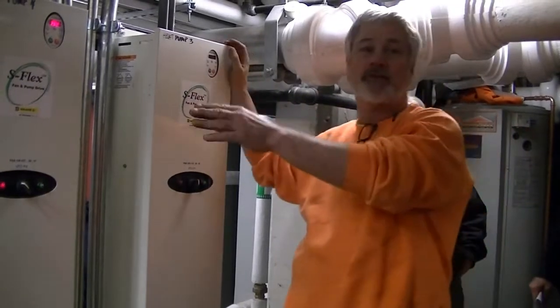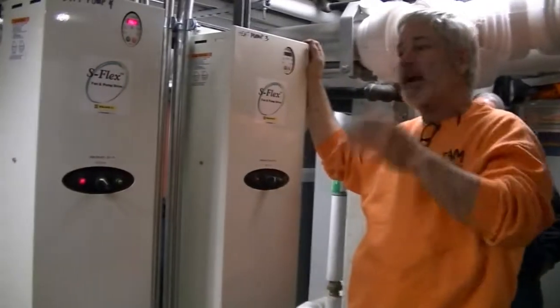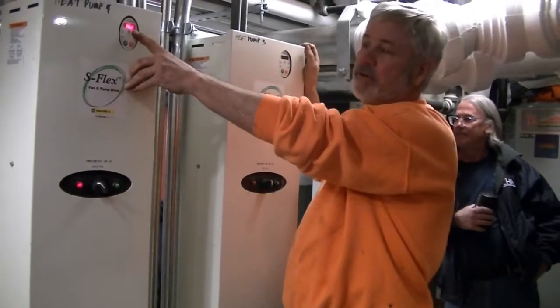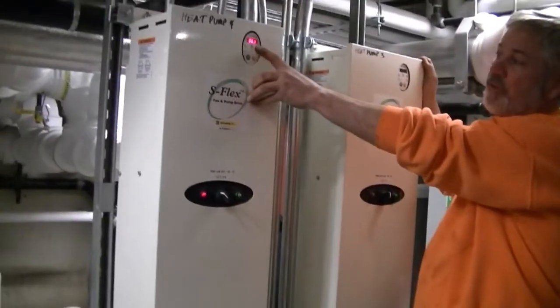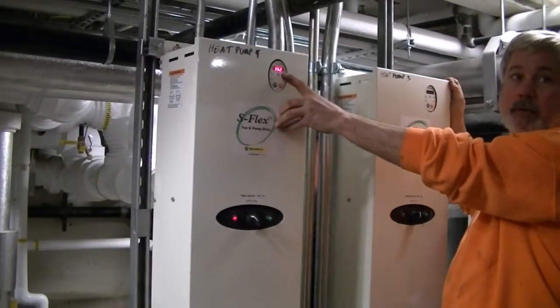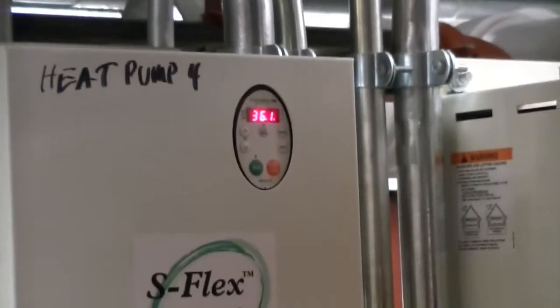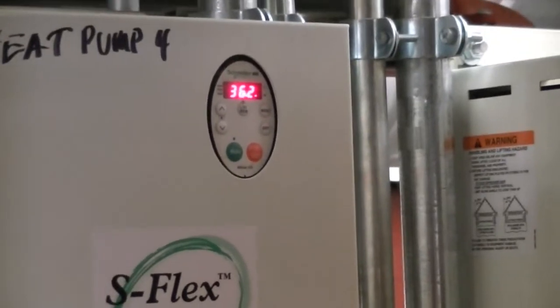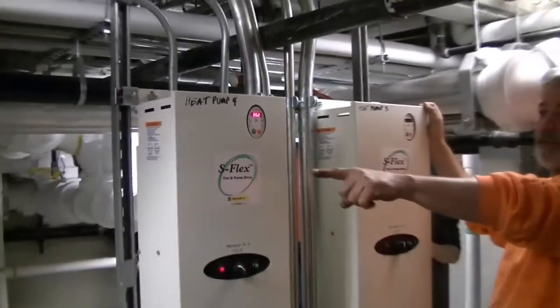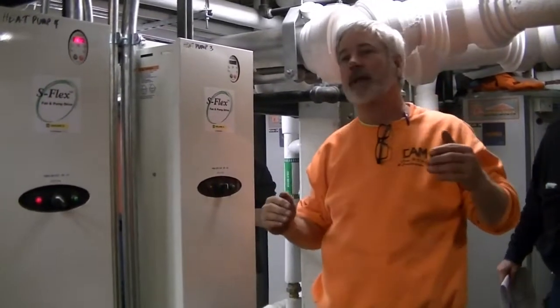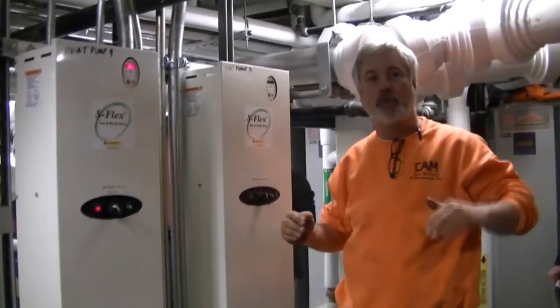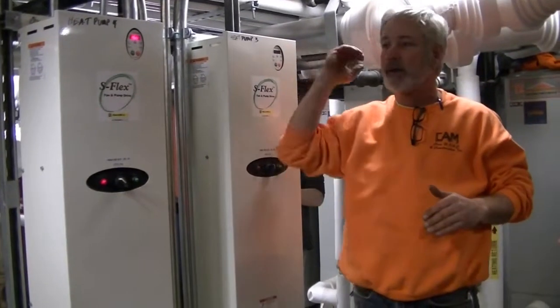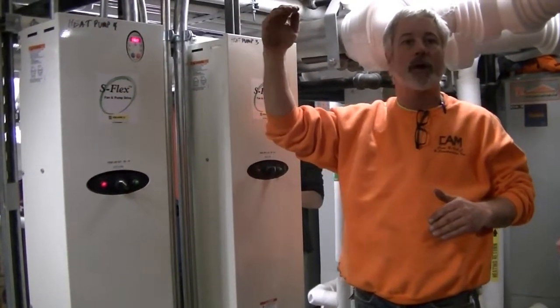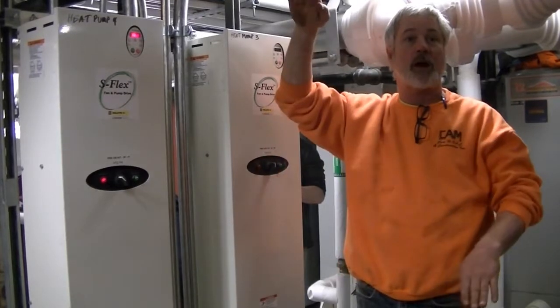That's done through the BMS system. The range on what you're seeing for a readout is actually how many hertz the motor is running at right now. That's how much is needed to maintain a 13 or 14 pound differential on the pumps. If the zone valves start closing down, suction pressure, the low side of the pump, starts going down, the high side of the pump discharge starts going up. So now your differential starts climbing.